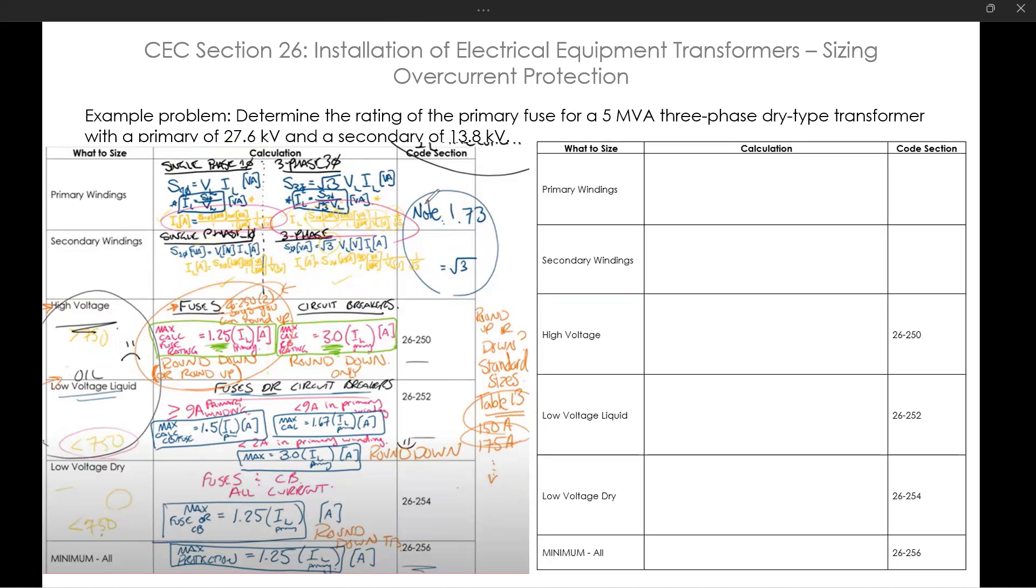Example: determine the rating of the primary fuse for a five MVA three phase dry type transformer with a primary of 27.6 kilovolts and a secondary of 13.8 kilovolts. So it's going to be a fuse, we have to take that from the question. And it's three phase.